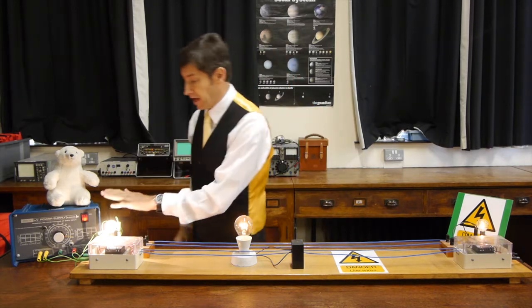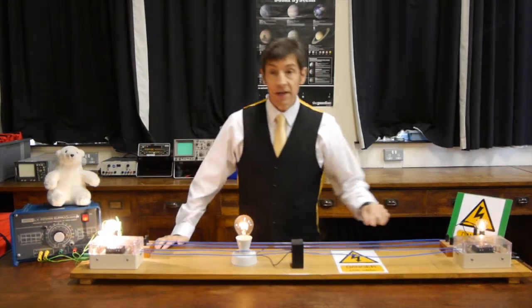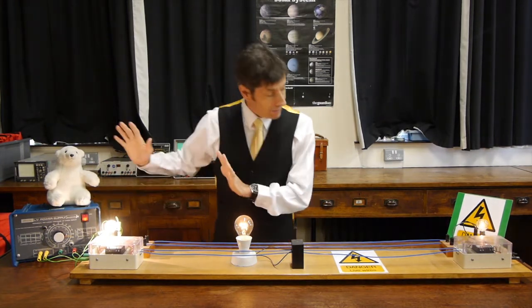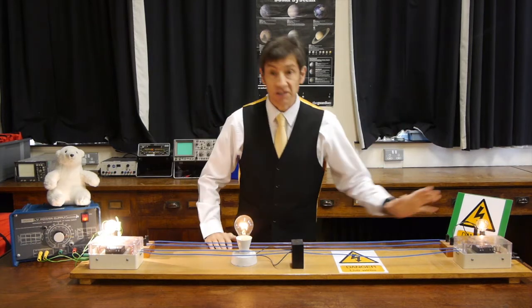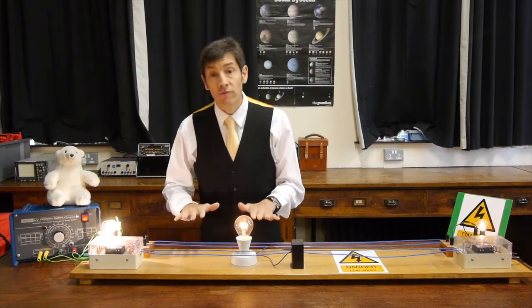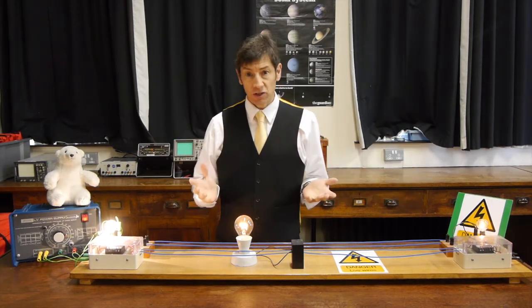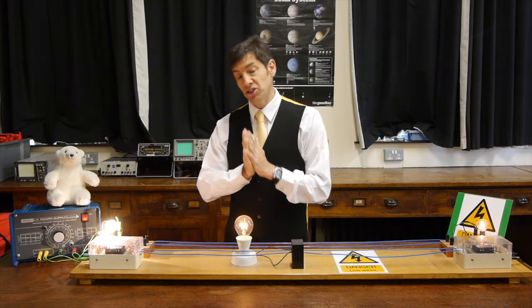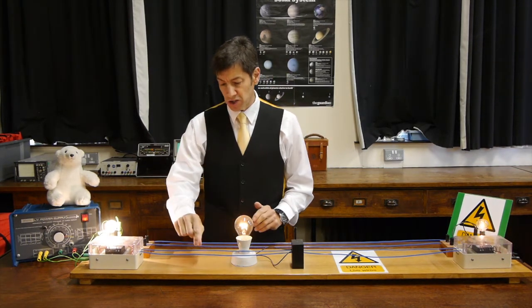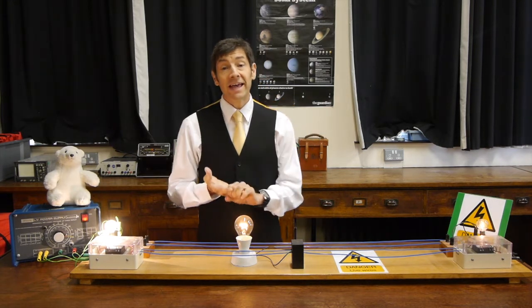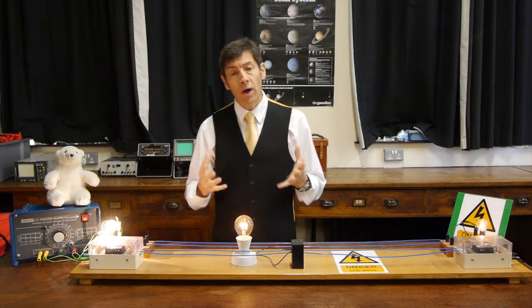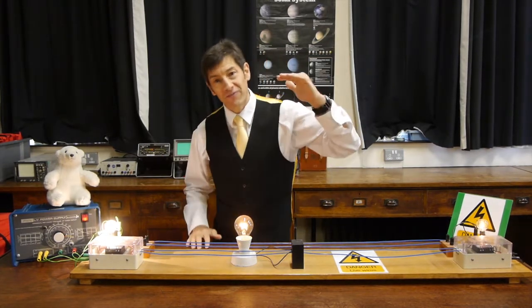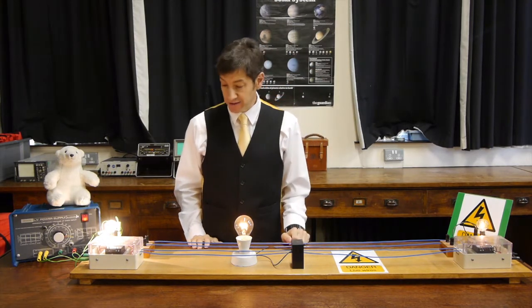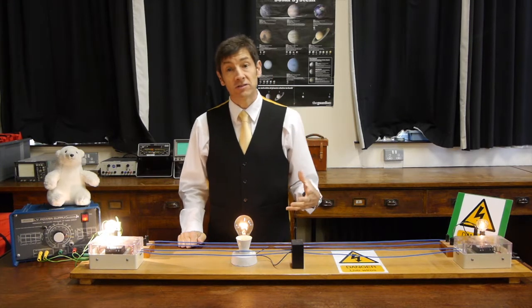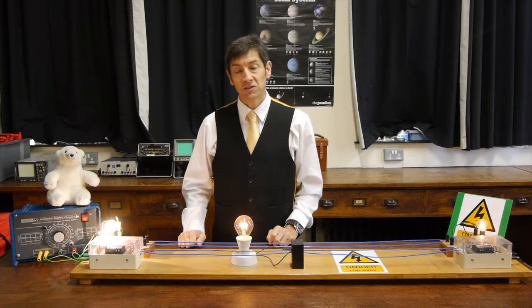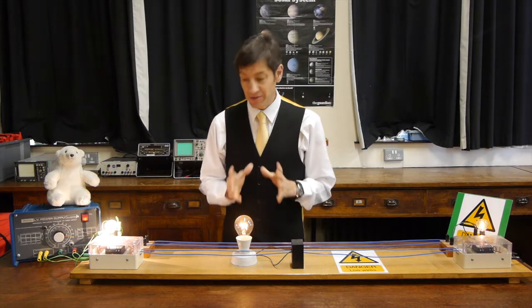If we used AC or DC on these power lines and transmitted at a low voltage, remember power to the houses is volts times amps. So if we've got a low voltage and a high power, we're going to have lots of amps, lots of current. Tesla's genius was to say: if we've got lots of current, the cables have to be thick and they'll get hot and lose energy. So why don't we step up the voltage, which reduces the current by the same factor. If we step up the voltage 10,000 times, the current in the cables will be 10,000 times less, and they won't get as hot.